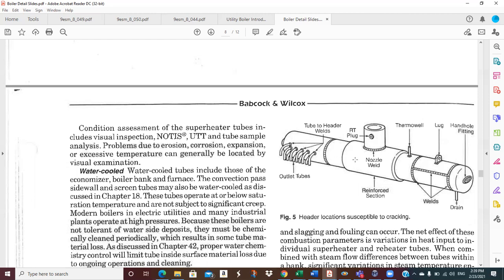Okay, and so guess what? All of these welds and all of these places are susceptible to cracking. They drill these holes, you know, there's a certain pattern, and then they hook the tubes in there. Well, you can get what they call header ligament cracking, which is cracking between these holes. And over time, these things can get so bad they have to be replaced. And these are not small pieces of steel. Can you imagine? You could have hundreds of boiler tubes coming in, stubbing into this thing.